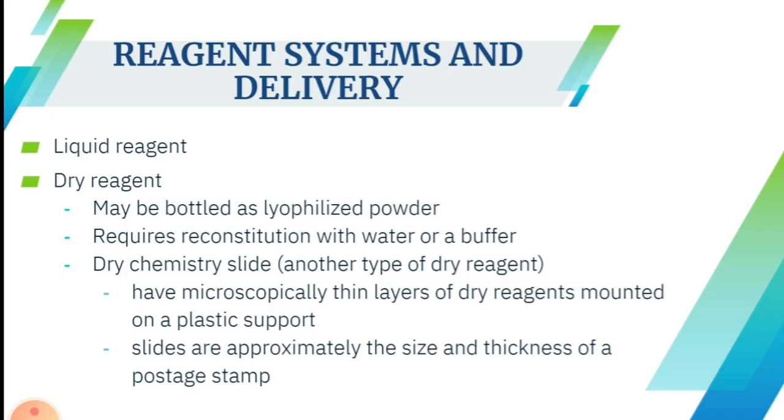A second and unique type of dry reagents is the multi-layered dry chemistry slide. For the Vitros analyzer, it was rebranded in 2001 as the Vitros microslide technology. So these slides have microscopically thin layers of dry reagents mounted on a plastic support, so the slides are approximately the size and thickness of a postage stamp. Reagent handling varies according to instrument capabilities and methodologies.